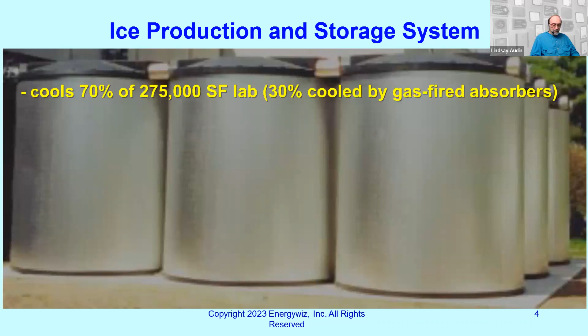The thermal storage system uses 350-ton screw chillers. They make 25-degree refrigerant. That's basically antifreeze. That's what it comes down to. You run the antifreeze through a coil inside these big tanks. It freezes the ice. Whenever you have a phase change, you know you have a great deal of energy being either added or subtracted. So you get a great deal of storage and very, very high density of storage when you go from chilled water to ice.